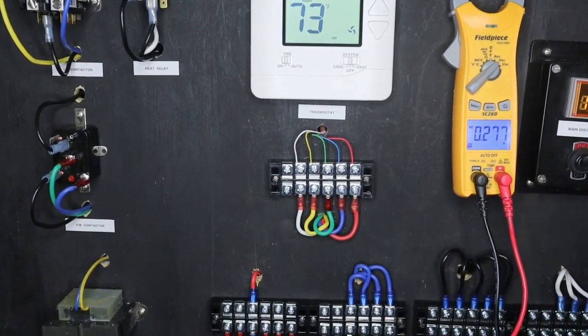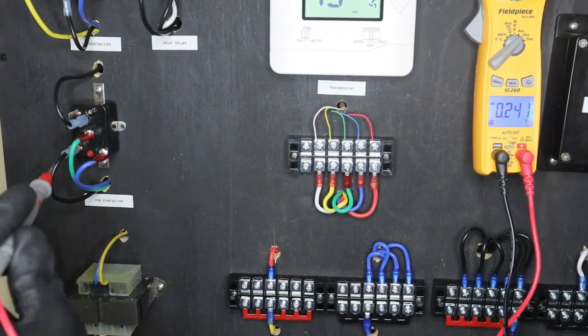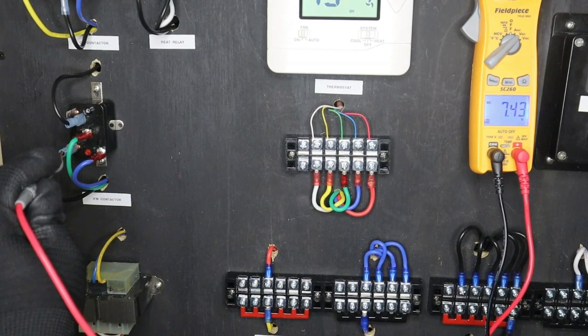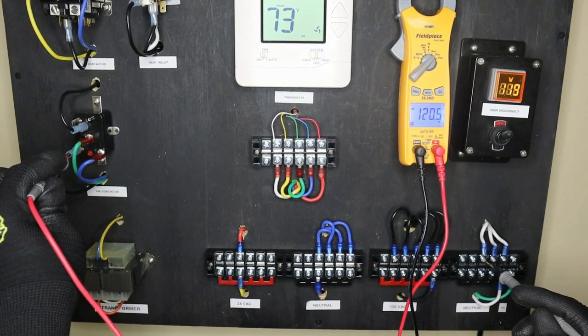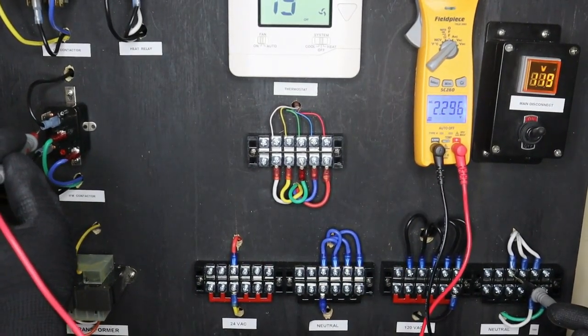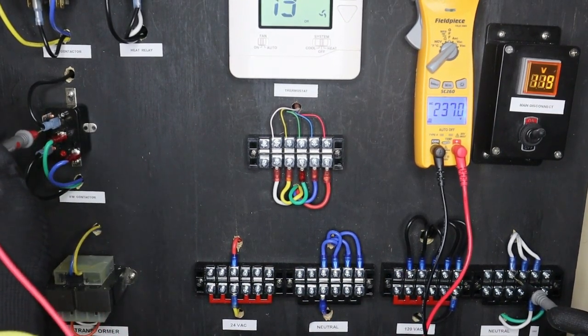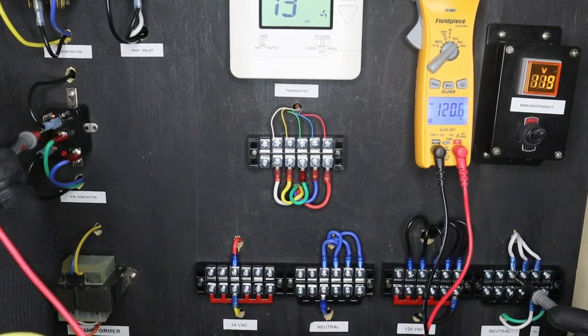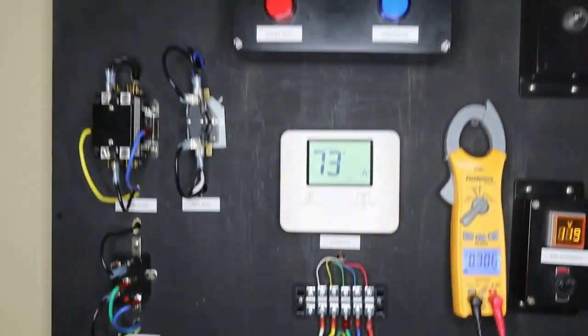Now let us check our incoming power to our fan relay. One lead goes to the incoming hot, one goes to neutral. So we are getting 120 volts. Let's check the output which was our normally open, but since we have power going to the coil this is now closed. So we have 120 volts AC at the output of our contactor thus energizing our indoor blower.